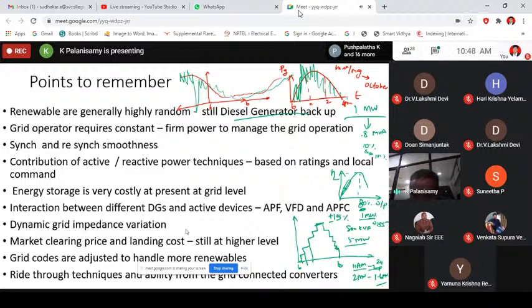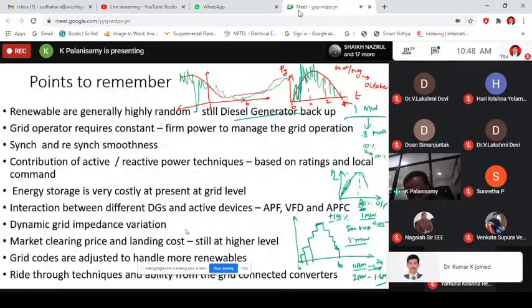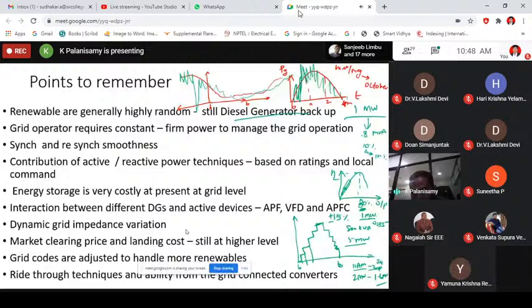So the solar inverters will start to inject higher order harmonics. Similarly, variable frequency drives will start to inject higher order harmonics, because you are connecting something in parallel to the source, so the system impedance came down, especially for higher order harmonics. So your characteristics will change. All those things you need to take care of when you are going for solar PV or wind or any other things.